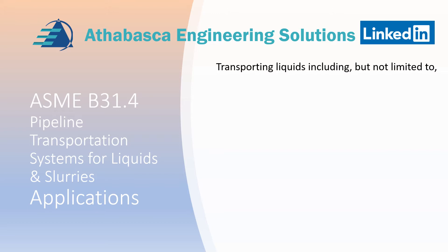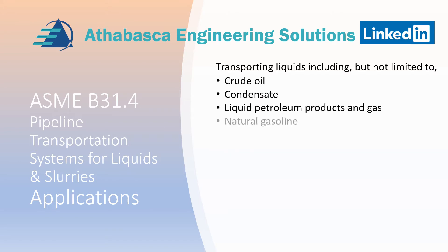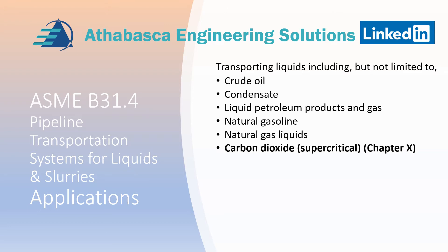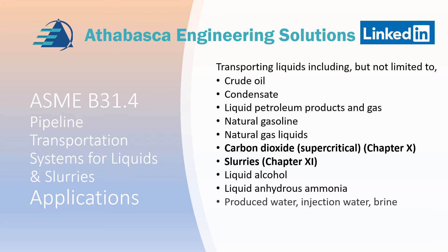B31.4 also has requirements for the types of liquids transported. The list includes crude oil, condensate, liquid petroleum products and gas, natural gasoline, natural gas liquids, carbon dioxide — such as supercritical CO2 for carbon sequestration in chapter 10 — slurries imported from B31.11, liquid alcohols, liquid anhydrous ammonia, produced water, injected water, brine, and biofuels. Please note these aren't exact definitions; you need to refer to the code.